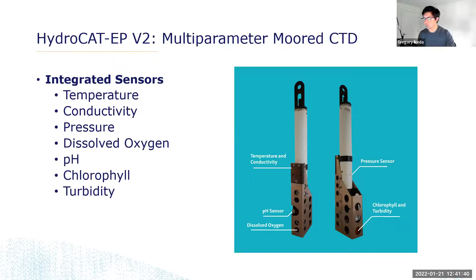That's doing a lot of good stuff. For one, in still water, you're pulling in a new sample to ensure that the temperature, conductivity, pH, and dissolved oxygen are actually from a new sample. It's not from water that's been entrained inside of the flow path. On top of that, it is aligning all of these things together. So you can be confident that the temperature, conductivity, pH, and DO that you're measuring is from the same parcel of water because it's sucking in that sample and holding it within the flow path. They're all aligned together, responding to the same thing.